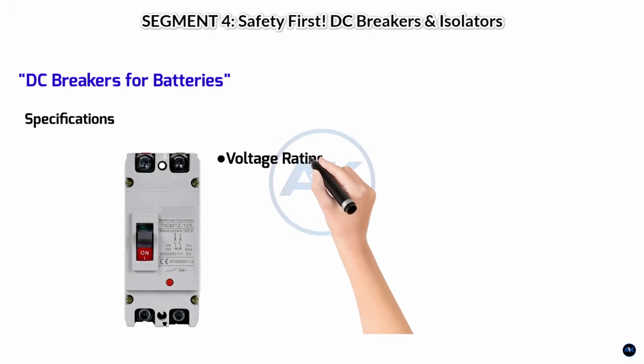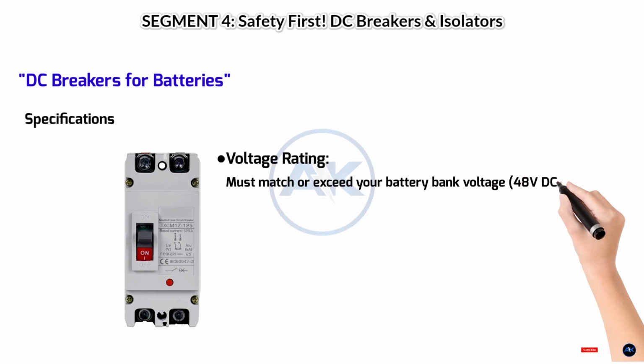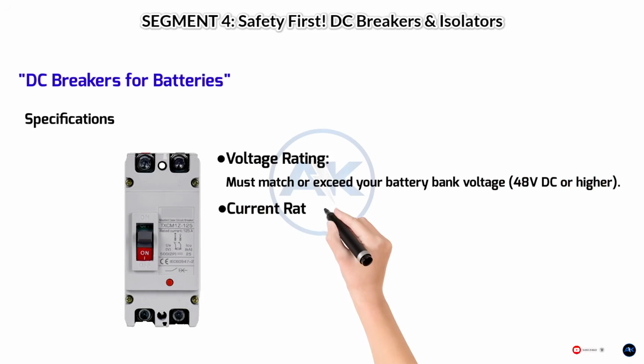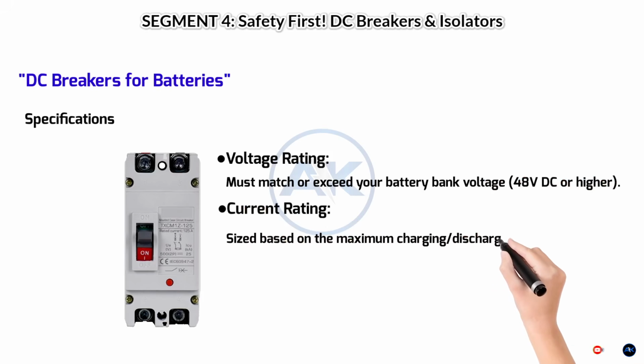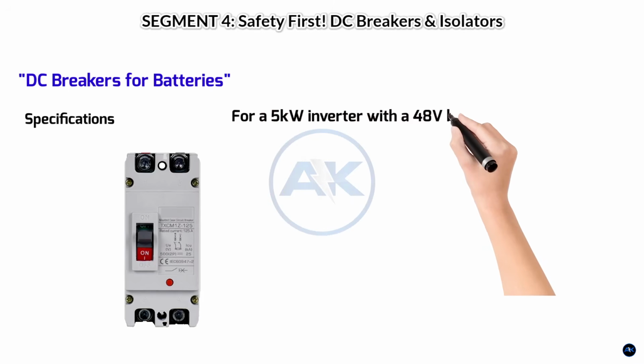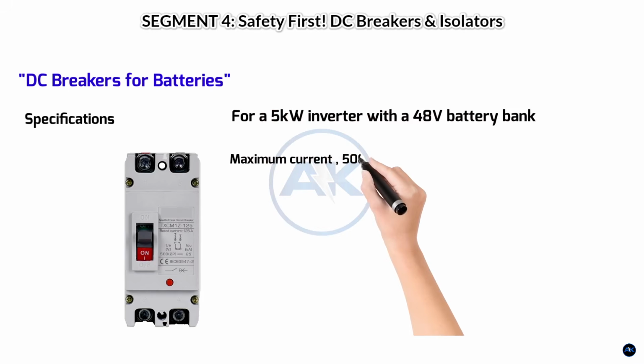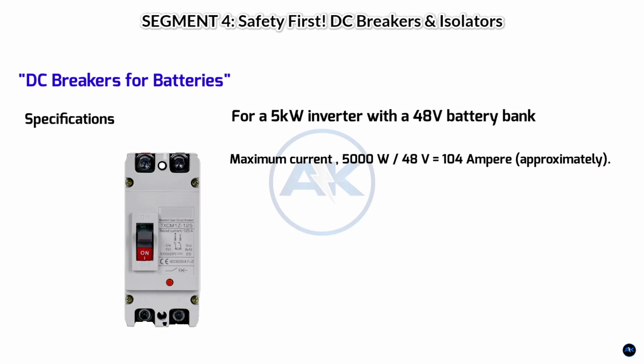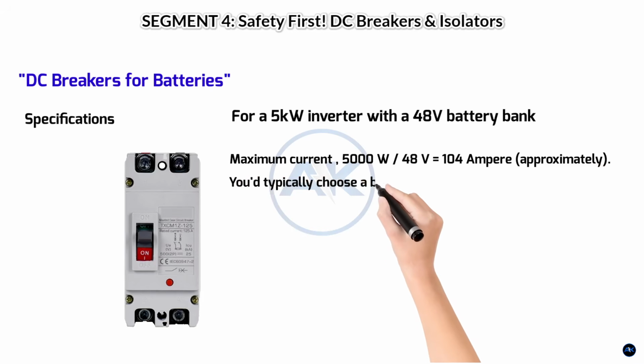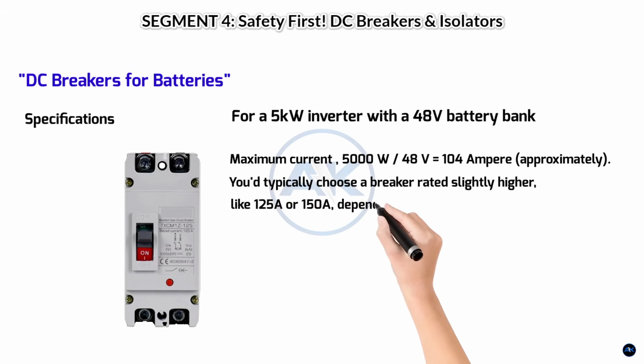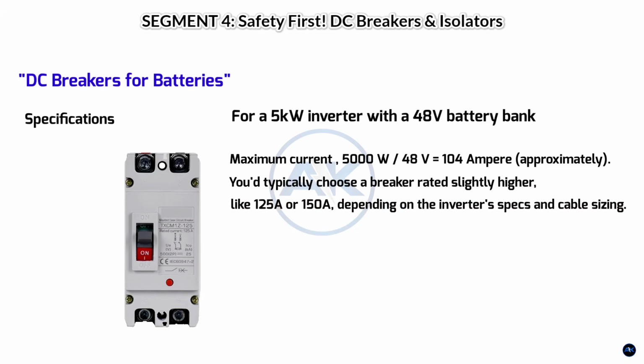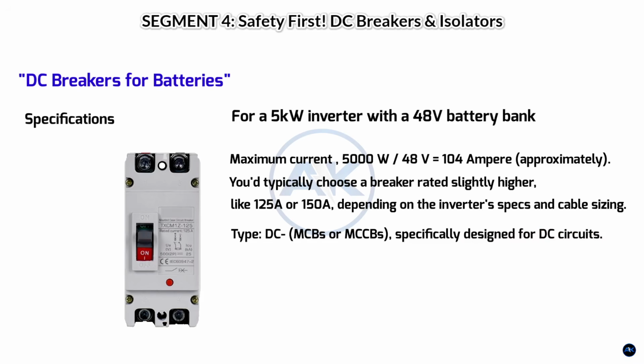Specifications. Voltage rating must match or exceed your battery bank voltage, 48 volts DC or higher. Current rating is sized based on the maximum charging or discharging current of your batteries and inverter. For a 5 kilowatt inverter with a 48 volt battery bank, the maximum current drawn from batteries can be 5000 watts divided by 48 volts equals 104 amperes approximately. You typically choose a breaker rated slightly higher, like 125 amps or 150 amps, depending on the inverter's specs and cable sizing. Type: DC rated circuit breakers, MCBs or MCCBs, specifically designed for DC circuits.